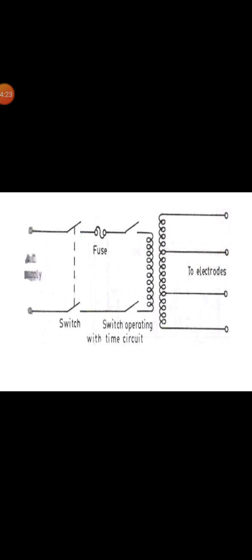This diagram shows the circuit of AC defibrillation, and an electronic timer circuit is connected to the primary of the transformer. The timer connects the output to the electrodes for a preset time. The timing device may be a simple capacitor and resistor network, which is triggered by a push button switch. The duration of the shock may vary from 0.1 to 1 second depending upon the voltage to be applied. For safety, the secondary coil of the transformer should be isolated from earth so that there is no shock risk to anyone.